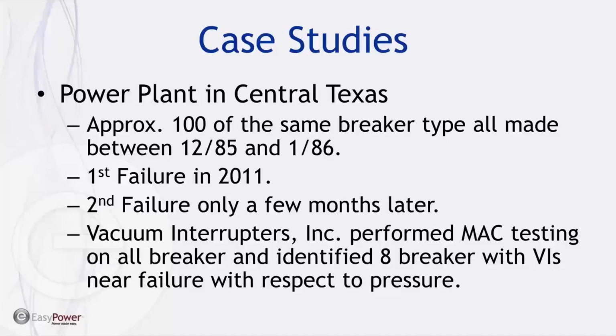We began to market our MAC tester in 2011, which coincidentally is when this power plant had their very first vacuum interrupter failure. They didn't think much of it. Just a few months later, they had their second vacuum interrupter failure, and this is since those circuit breakers were installed. So this made them very worried, and they contacted us and asked us to come and test all of the circuit breakers that they had of this type.